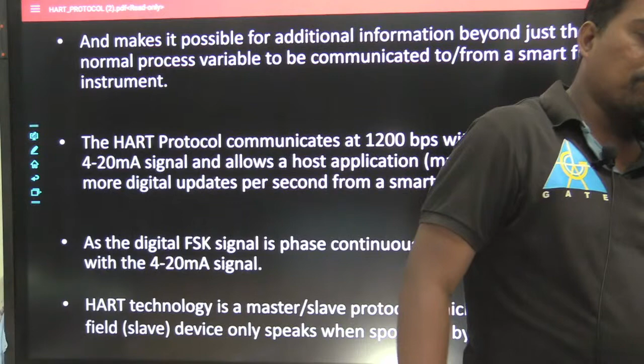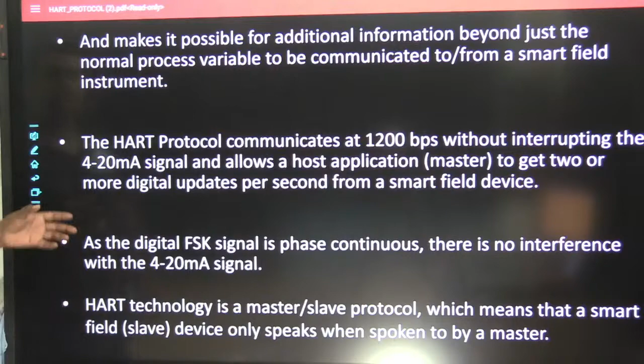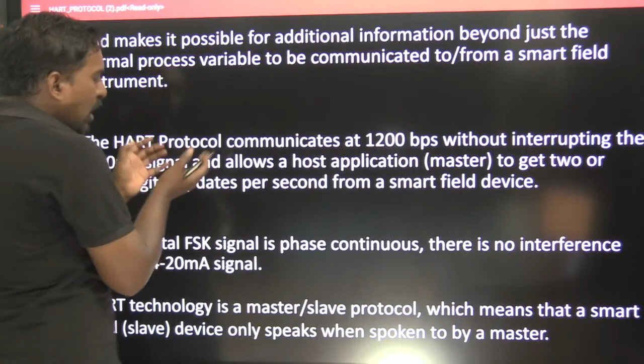Here, not only the data of the sensor, if you want to make some configuration to that sensor, you can do that from the master. That means you can take the sensor and the field device as a slave and the PLC DCS system as a master. See here, the HART protocol communicates at 1200 bps without interrupting the 4 to 20 milliampere signal and allows a host application, which is called master, to get 2 or more digital updates per second from a smart field device. The smart field device can be taken as a sensor.